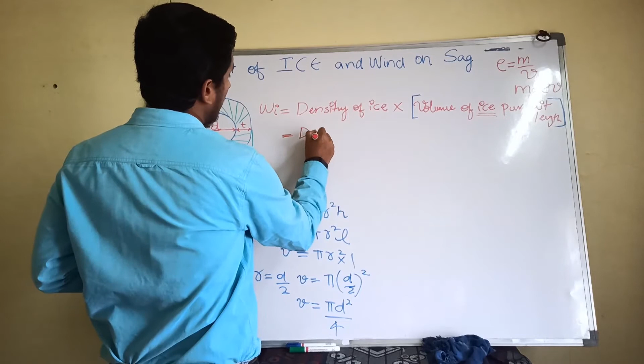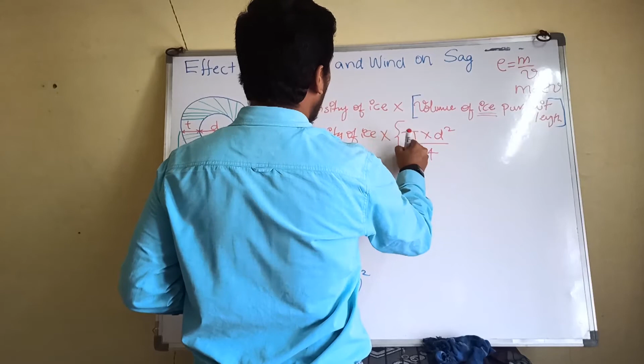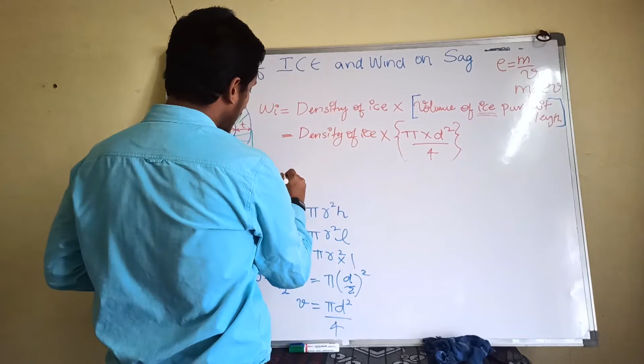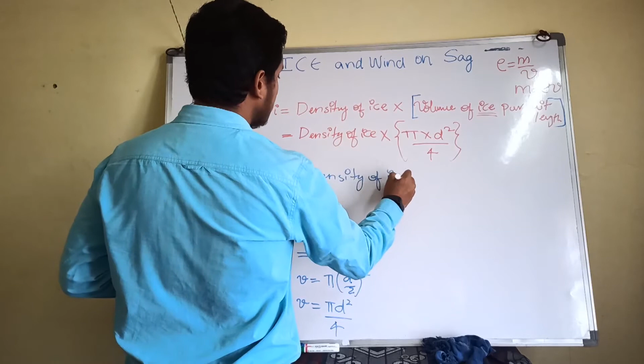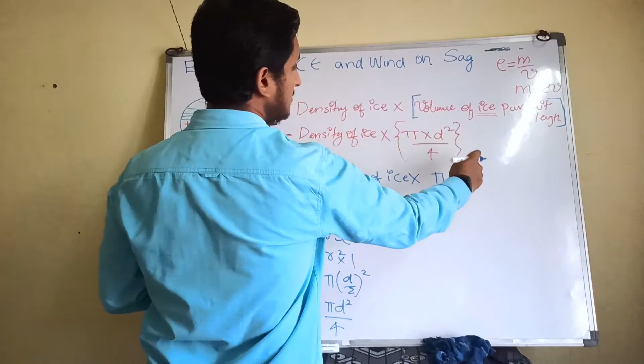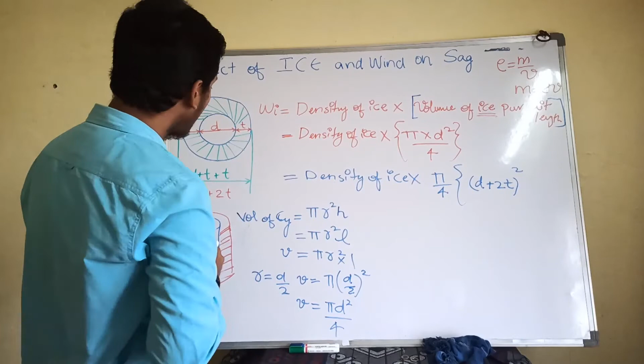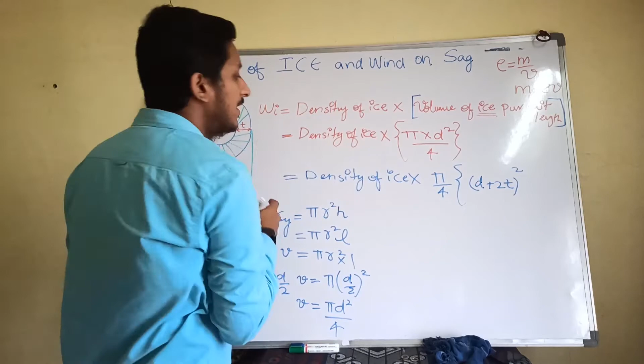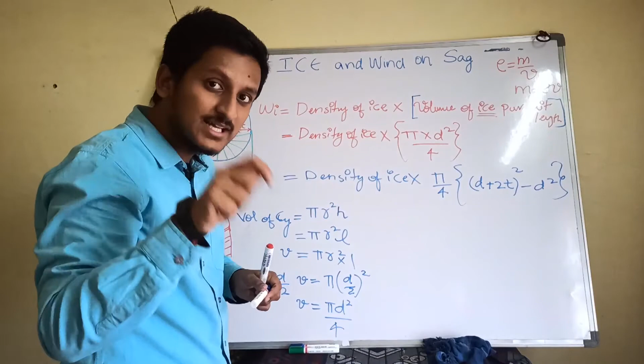So I will write density of ice into, what is the volume of ice per unit length? That is pi d square by 4. Now how am I going to write this? You have to see now. Again I will write density of ice into pi by 4. Now d square is there. I am going to substitute this d plus 2t in this d square. So what will happen? (D plus 2t) whole square. Okay. Now I have substituted this here. Now can I say, if I remove this part, that means the conductor material part, d square from this, I will get the exact volume of the ice per unit length. So it is per unit length. So what am I going to do? Into 1. Reducing it, what we will get?